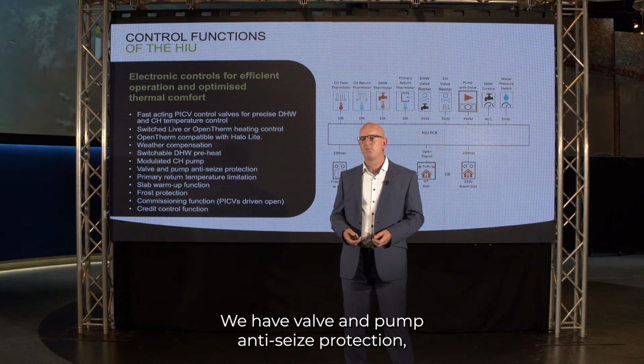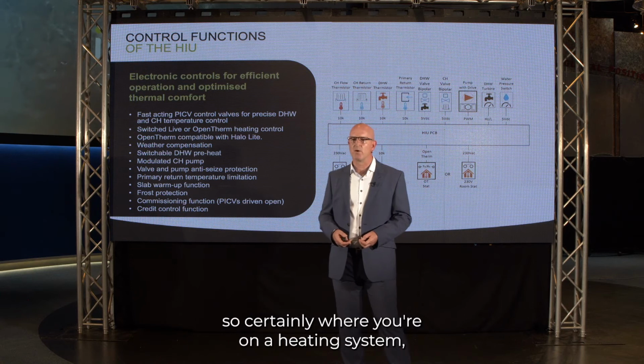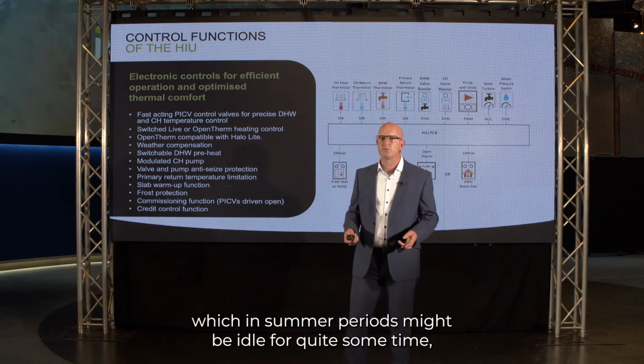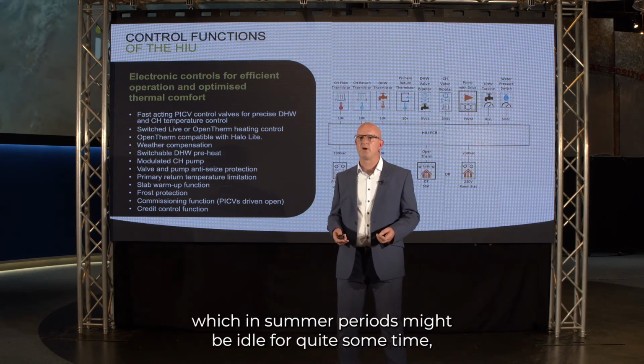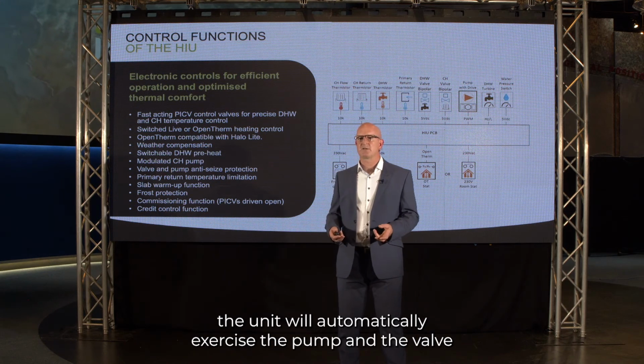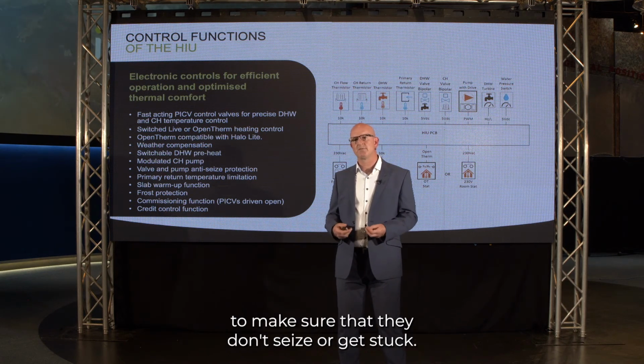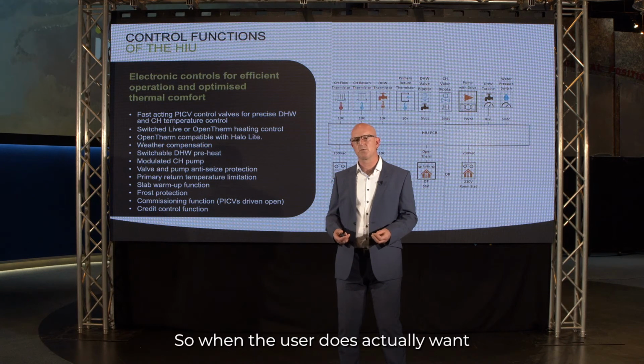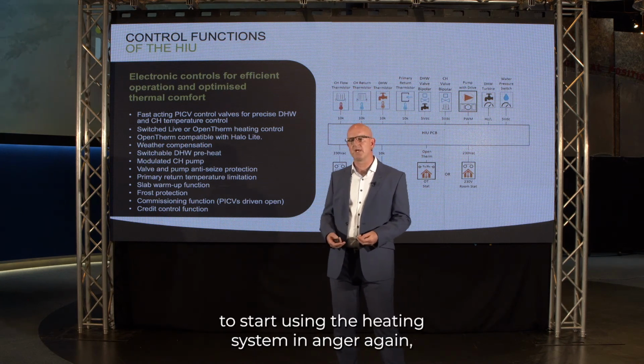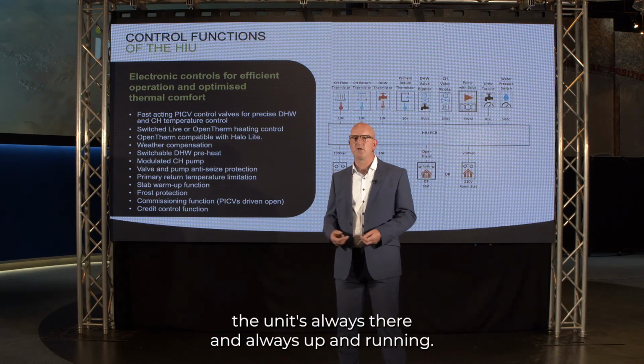We have valve and pump anti-seize protection, so certainly where you're on a heating system which in summer periods might be idle for quite some time, the unit will automatically exercise the pump and the valve to make sure that they don't seize or get stuck. So when the user does actually want to start using the heating system in anger again, the unit's always there and always up and running.